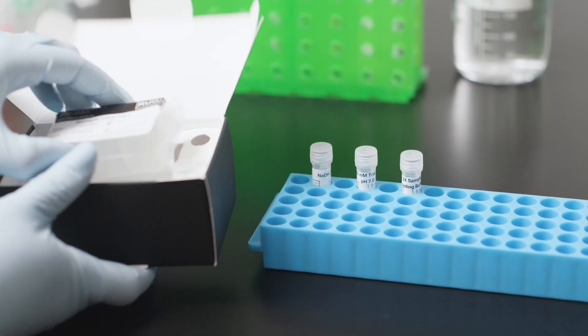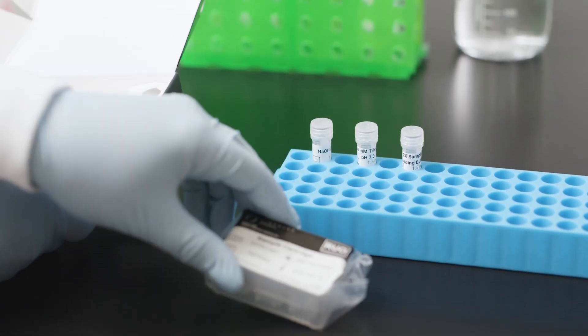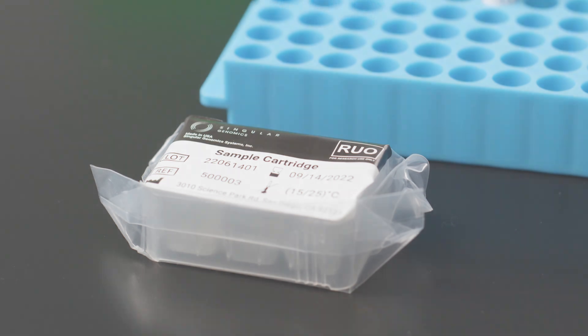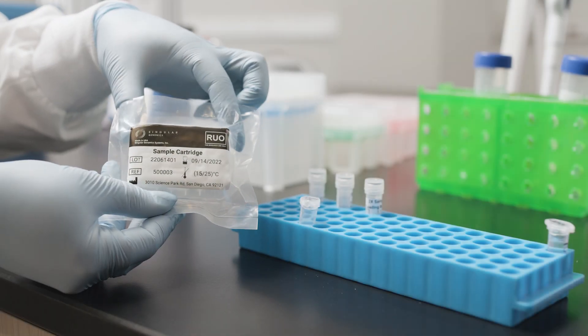Do not expose the sample cartridge to light for any extended period, as this can compromise the stability of the diluted bleach solution contained in the sealed wells of the cartridge. Remove the cartridge from its plastic bag.